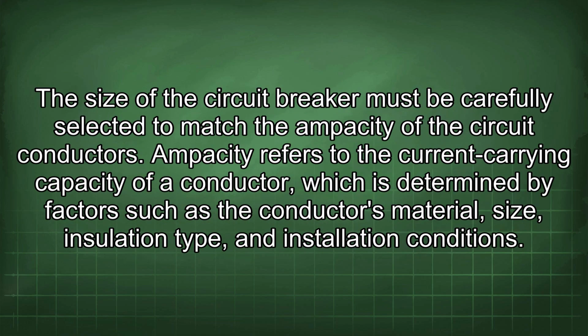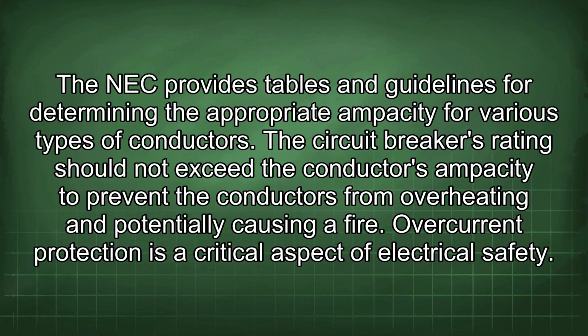The size of the circuit breaker must be carefully selected to match the ampacity of the circuit conductors. Ampacity refers to the current carrying capacity of a conductor, which is determined by factors such as the conductor's material, size, insulation type, and installation conditions. The NEC provides tables and guidelines for determining the appropriate ampacity for various types of conductors. The circuit breaker's rating should not exceed the conductor's ampacity to prevent the conductors from overheating and potentially causing a fire. Overcurrent protection is a critical aspect of electrical safety.